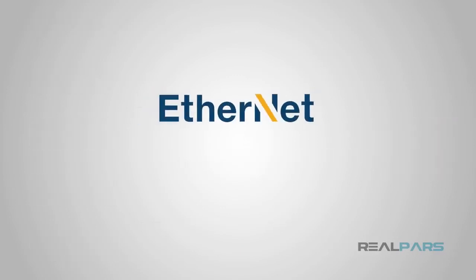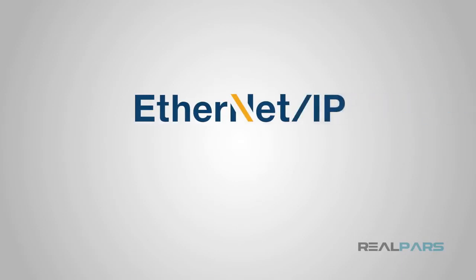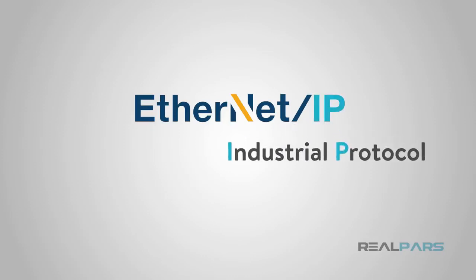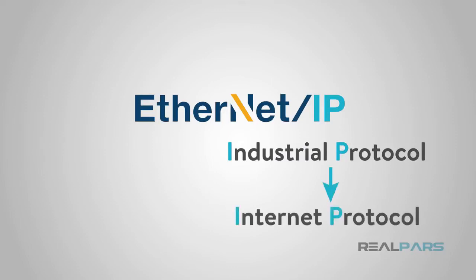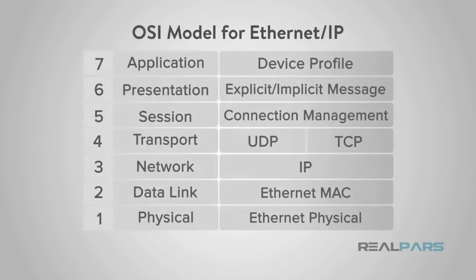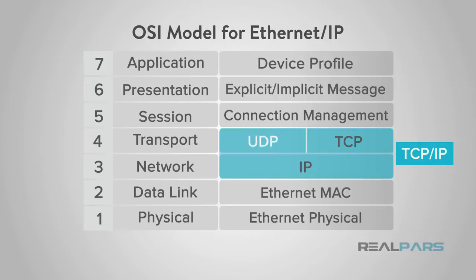Now that we have explained the Ethernet packet, we can get into the IP part of the Ethernet IP, or EIP description. IP in this case now correlates to industrial protocol versus the previous description of Internet protocol. Confused yet? The IP part of this protocol is simply the use of the Ethernet infrastructure in conjunction with the industrial protocol, which uses Common Industrial Protocol, or CIP layers, that combine with TCP/IP, or User Datagram Protocol, or UDP layers, to create a protocol that can be used to support data exchange and control applications.